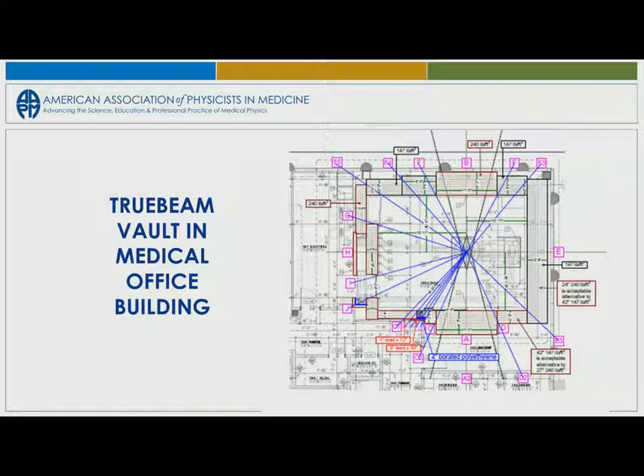So it's much better if you can put your opening off here to the side so that somebody walking by here doesn't see that patient when that door comes open. What they had to do was actually go through and put a little partition there so that the patient was not visible to the general public walking down the hallway. So there's pluses and minuses to some of these designs, but that's what you can wind up doing, using your HD concrete, using your sliding doors. And what I'm saying is, look at the space. This is a fairly compact space. It takes much less room than doing a traditional maze linac.